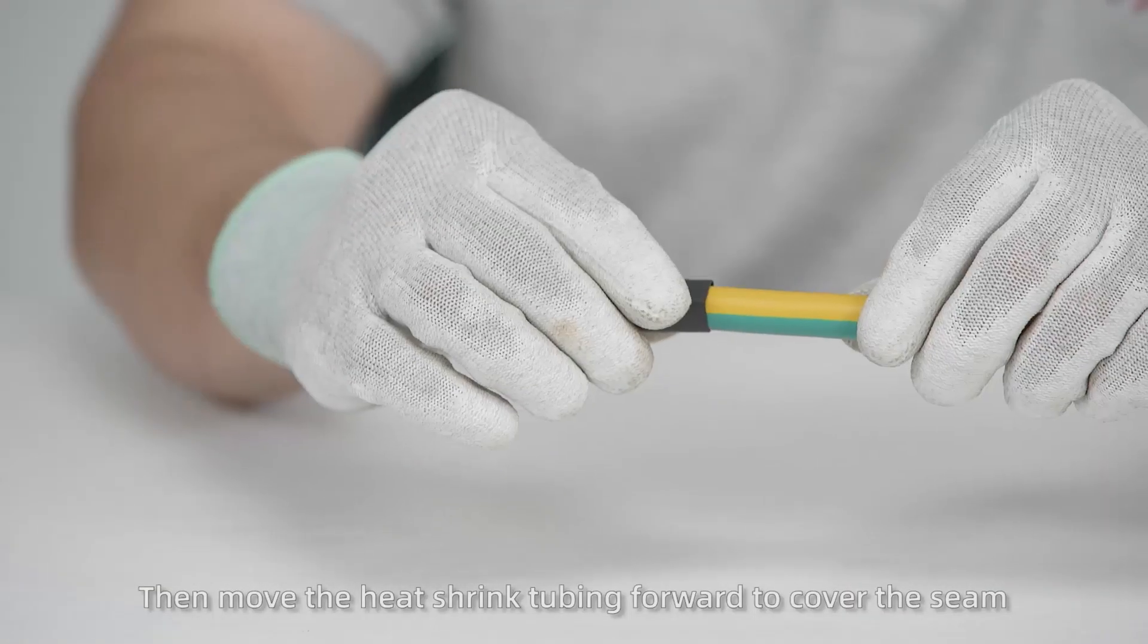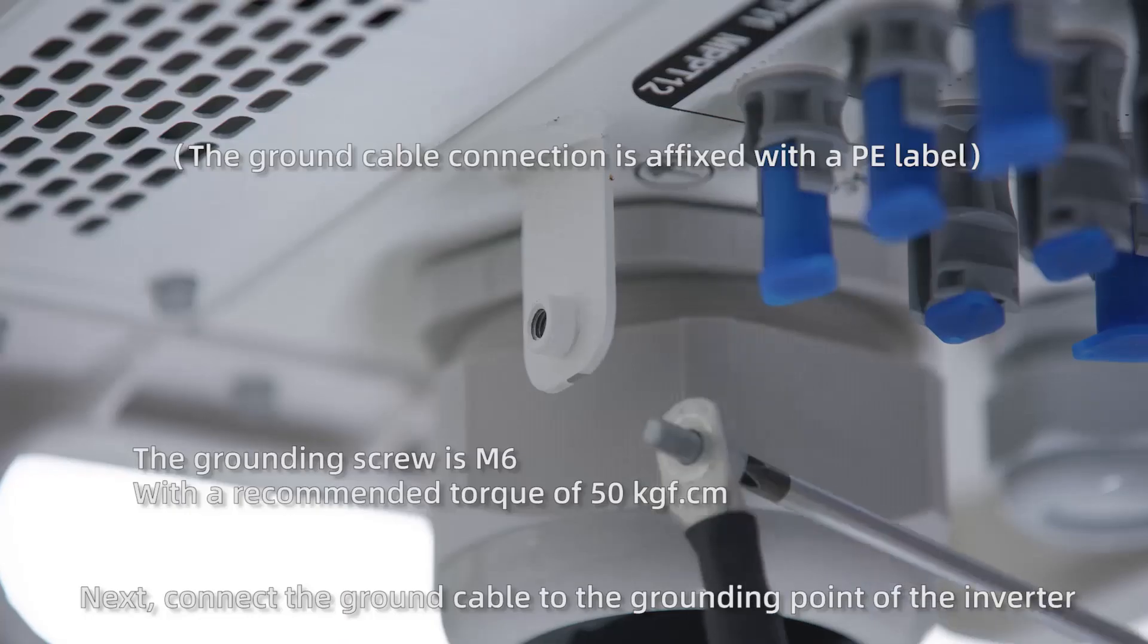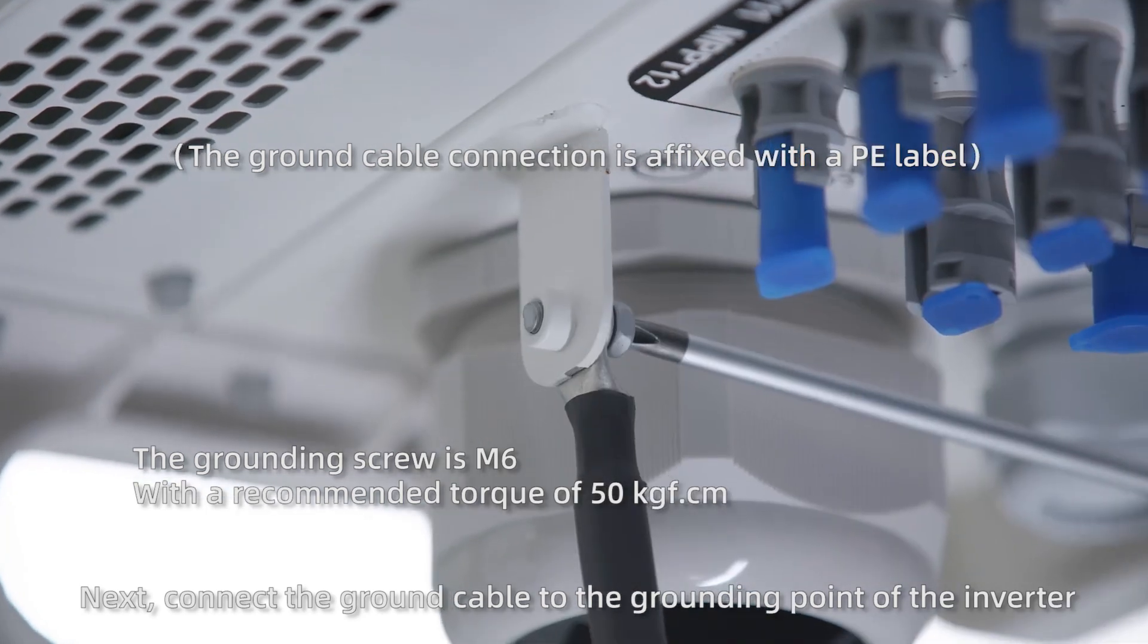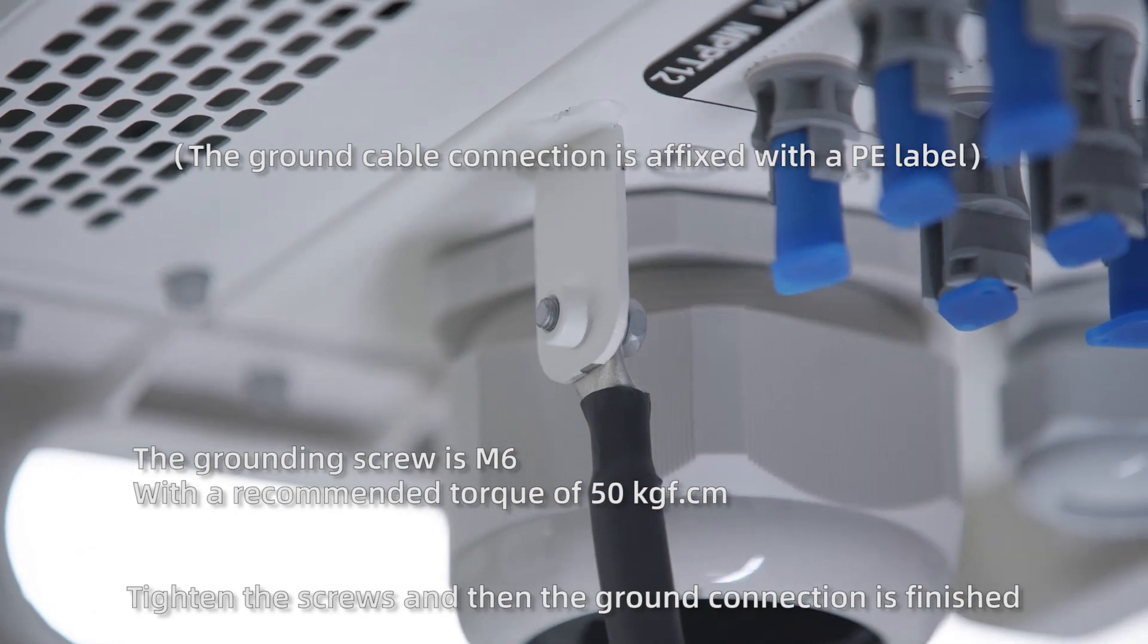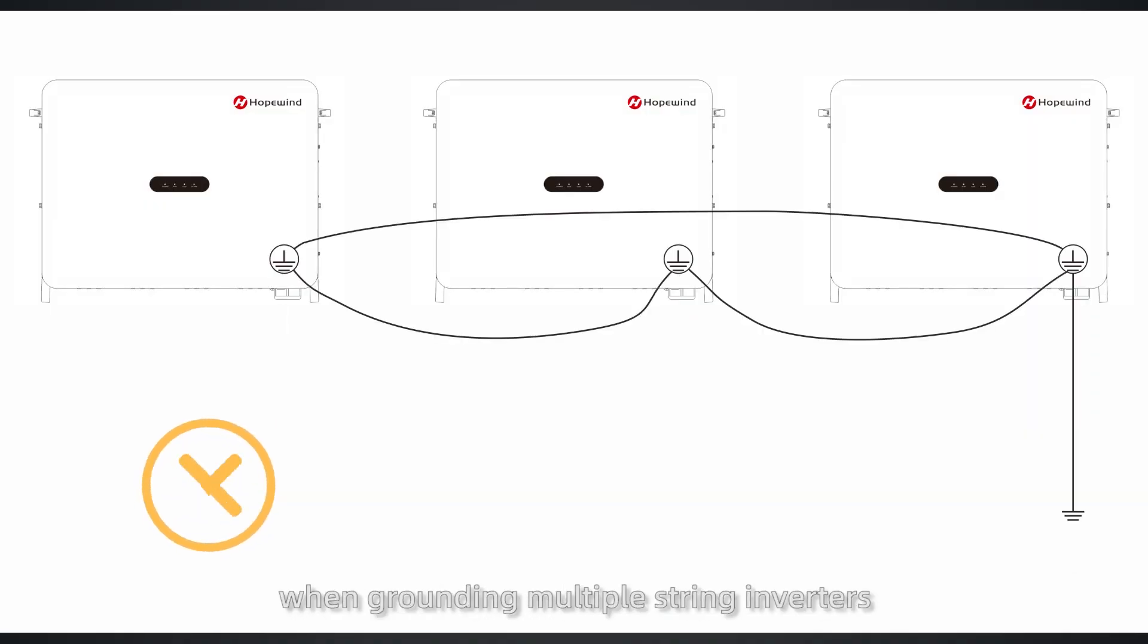Then move the heat shrink tubing forward to cover the seam, and use a dryer to heat the tubing to make it tight. Next, connect the ground cable to the grounding point of the inverter. Tighten the screws, and then the ground connection is finished. Please adopt single point grounding when grounding multiple string inverters.